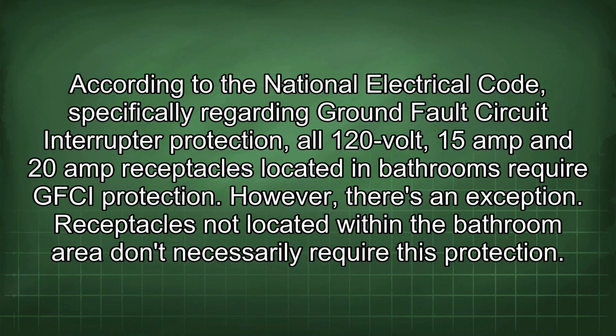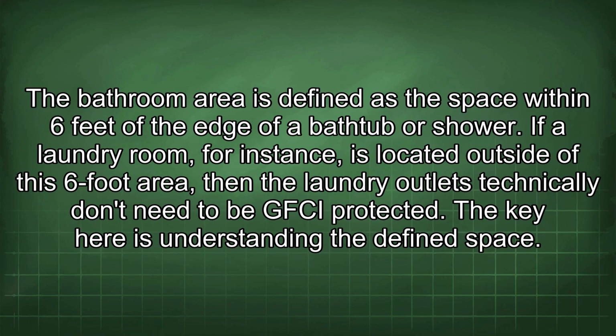According to the National Electrical Code, specifically regarding ground fault circuit interrupter protection, all 120-volt, 15 amp and 20 amp receptacles located in bathrooms require GFCI protection. However, there's an exception. Receptacles not located within the bathroom area don't necessarily require this protection. The bathroom area is defined as the space within 6 feet of the edge of a bathtub or shower.